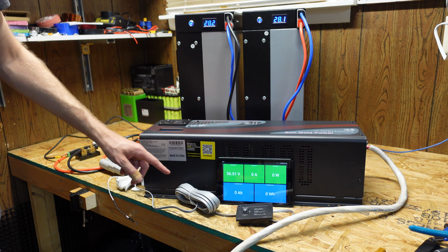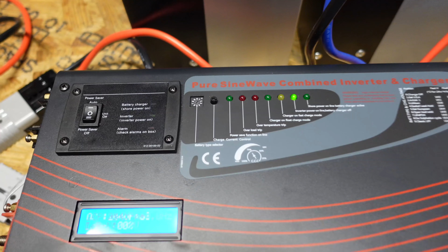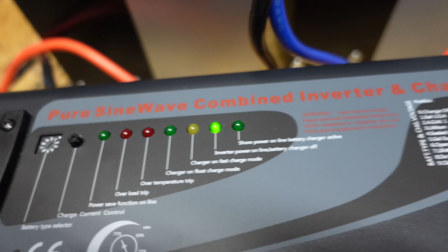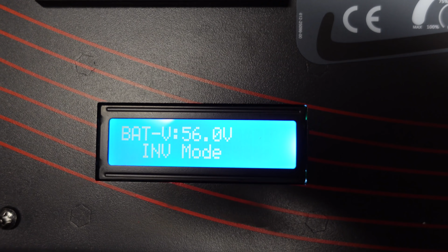This is pretty much the only disadvantage to these low frequency inverters: the idle consumption. With no load plugged in, we're sitting at 104 watts currently. Looking at the top of the inverter, this green light means inverter on, battery charger off, and the display cycles through a few different statuses.